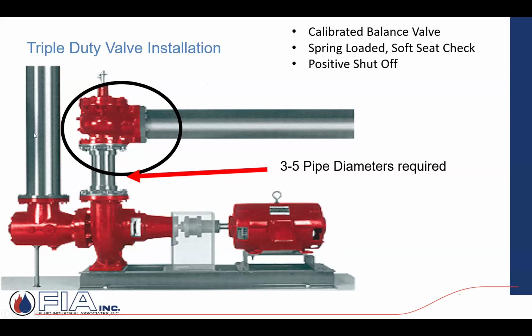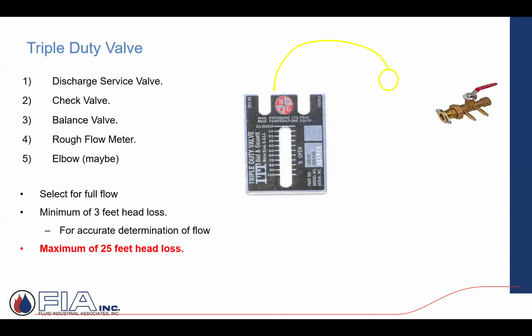And then you're going to have a valve back here, a butterfly valve of some sort, that's going to close to isolate the pump from the system. It's going to be a soft-seated check to prevent reverse flow, especially if you had 2 pumps in parallel. You don't want one pump running backwards through the off pump. The check will check that. And then it can also act as a balancing device.